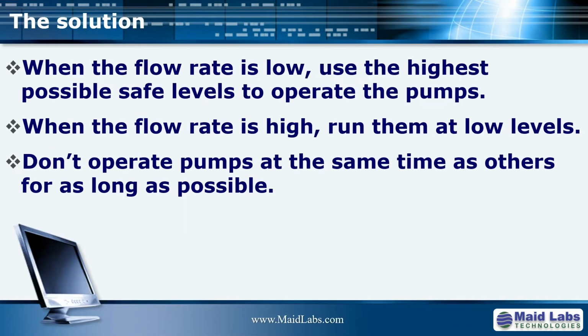The key here to be able to reduce the cost of operating a lift station, other than finding problems earlier, is that when the flow rate is low, run the pump at the highest possible level of operation within the lift station.